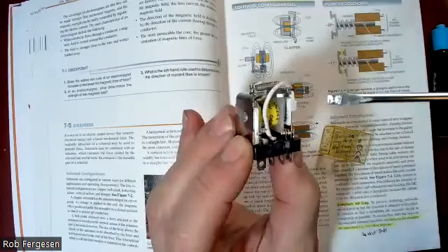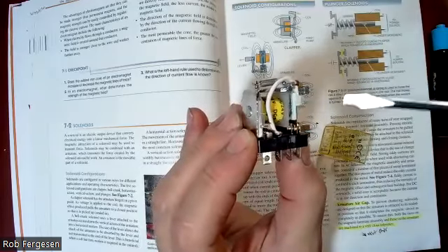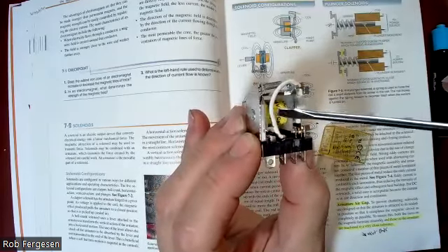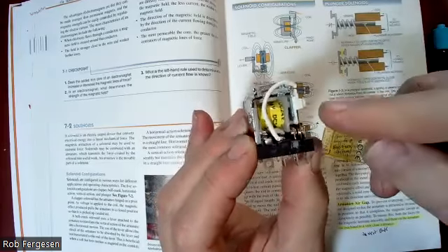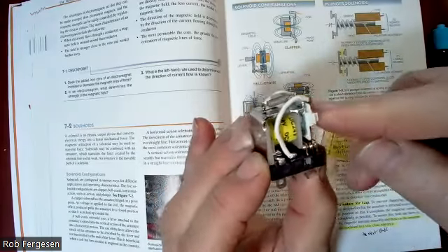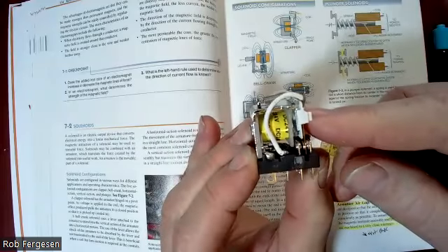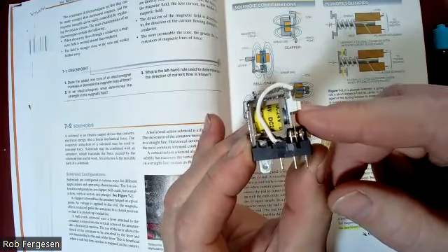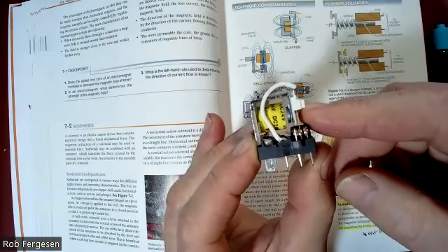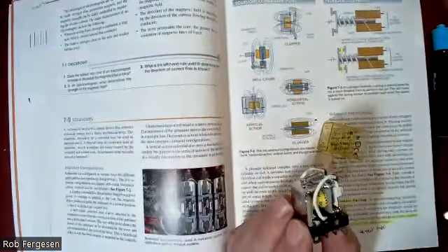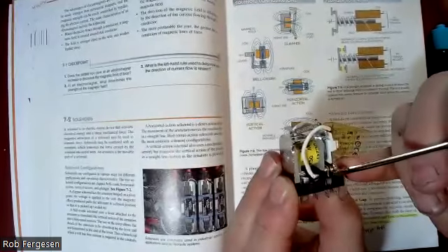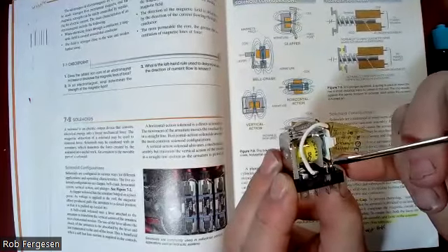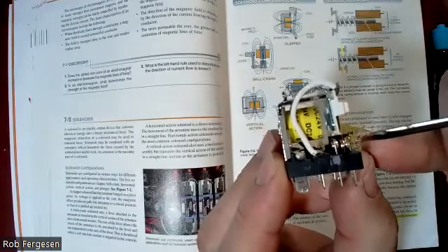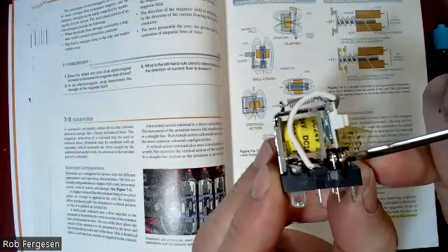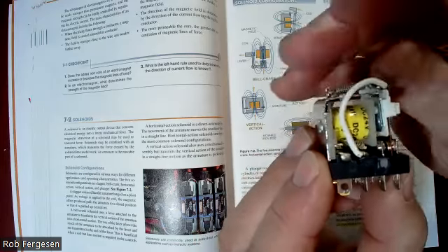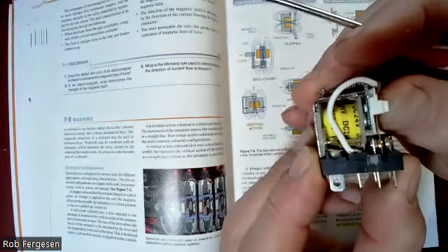That sucks this plate. There's a magnetic plate right here. When that turns on, it creates a magnetic field and sucks this plate across against it. You can see it doesn't have far to throw. That plate just goes right up against it. And that coil right there creates the contact closure between that contact and that contact. See, normally closed are these two contacts, normally open are these two, until it turns on, and then they close.